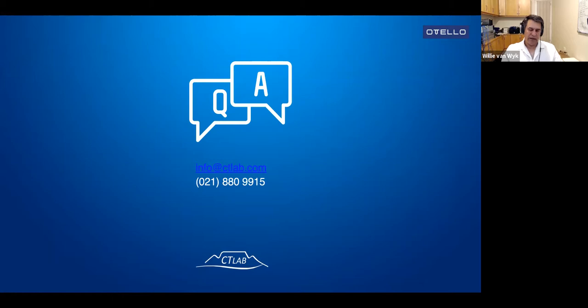Just a comment there as well. You can install a low power VT in the cable area when a cable comes from the trenches into your switching cabinet. On the C-type bushings, depending on whether there's enough space, at the back of the boot you can screw in a VT. It's as simple as that.